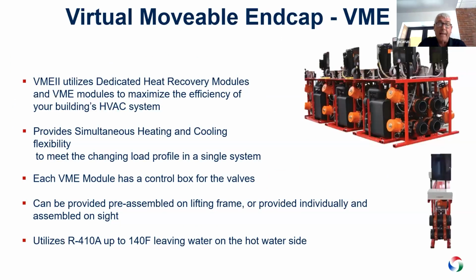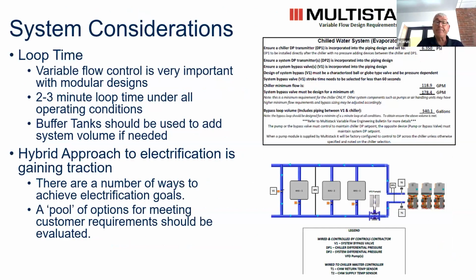This is what it looks like. Standard modules, the orange valves open and close depending on how much heat recovery you're able to do based on the size of the load. Currently 410A, again, headed for 454B and 513A, and using variable speed compressors. We've been doing that for about 4 or 5 years now in this module with a Danfoss true variable speed version with a coordinated drive and compressor combination.